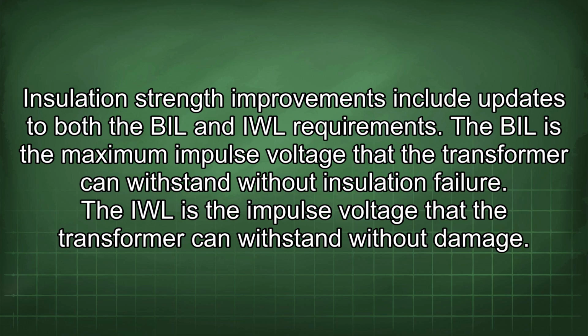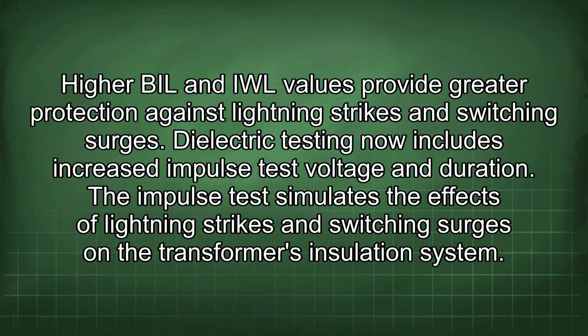The IWL is the impulse voltage that the transformer can withstand without damage. Higher BIL and IWL values provide greater protection against lightning strikes and switching surges. Dielectric testing now includes increased impulse test voltage and duration. The impulse test simulates the effects of lightning strikes and switching surges in the transformer's insulation system.